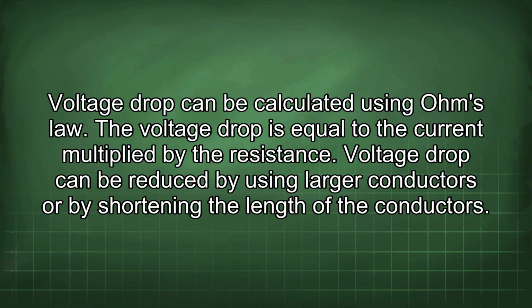Voltage drop can be calculated using Ohm's law. The voltage drop is equal to the current multiplied by the resistance. Voltage drop can be reduced by using larger conductors or by shortening the length of the conductors.